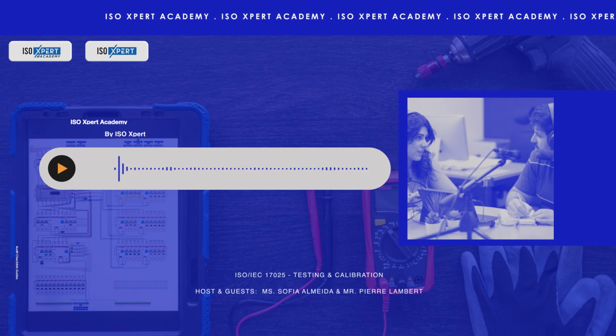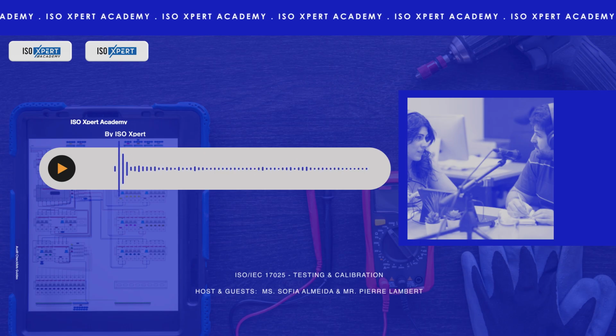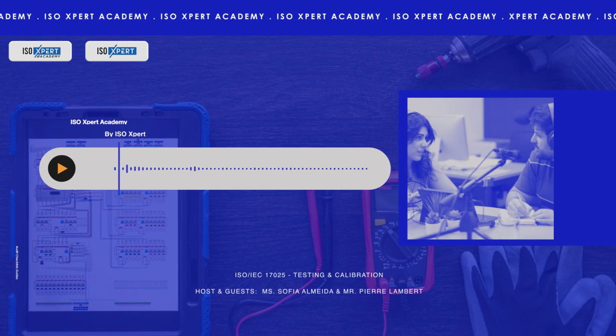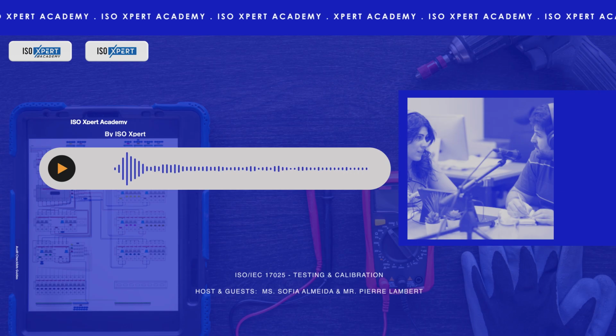They need defined procedures. For what exactly? For identifying and reviewing any work that doesn't meet the requirements, whether it's their own requirements or the customer's. Then, making necessary corrections. And, importantly, evaluating if clients need to be notified, maybe if their results were potentially affected. And auditors want proof this happened.